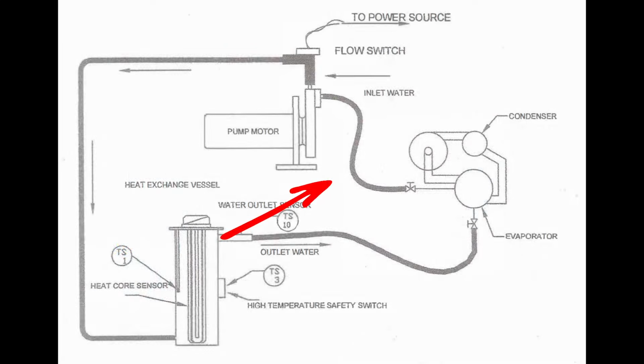And just to show you some additional detail on how this is going to look inside. So you've got your machine. We're pulling off the evaporator. We're going to pull into our pump. We're going to push that through into the heat chamber. It's going to heat that water up, send it back out, and it's just going to constantly recirculate on that heat exchanger until we eventually hit our pressure set point.